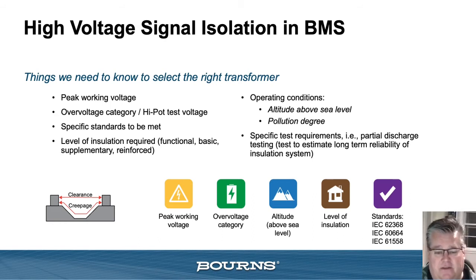Distance per a safety standard is in terms of creepage and clearance. Clearance is defined as the distance between two objects or two parts of the transformer through air alone. Creepage is the distance between two different surfaces, or two different points along a surface, so not just through air. It takes into account different criteria per the table in the standard. Those combinations of things, and also the level of insulation, which from a customer aspect we'll ask about: does it need to meet a functional level of insulation, where the transformer only needs to operate in circuit? That means it would be dedicated to a lesser amount of creepage and clearance distance, as opposed to a reinforced isolation requirement, which has three layers of user protection from electric shock. That obviously is going to need an increase of physical distance per the table in the standard.